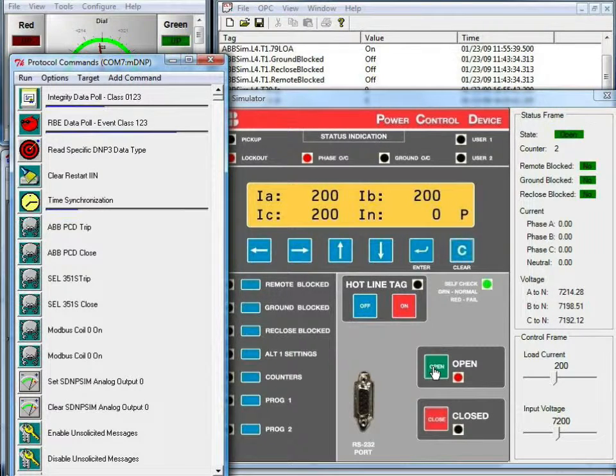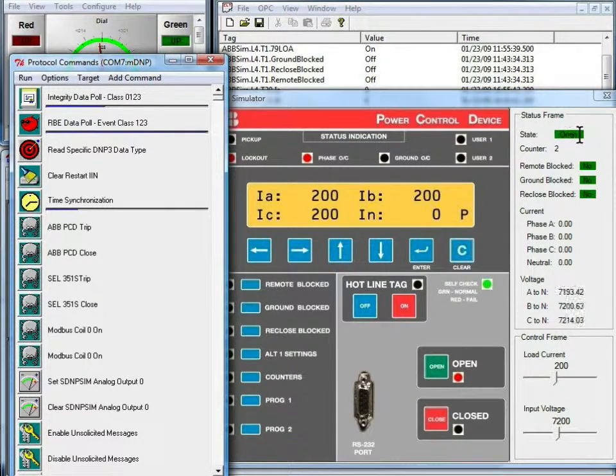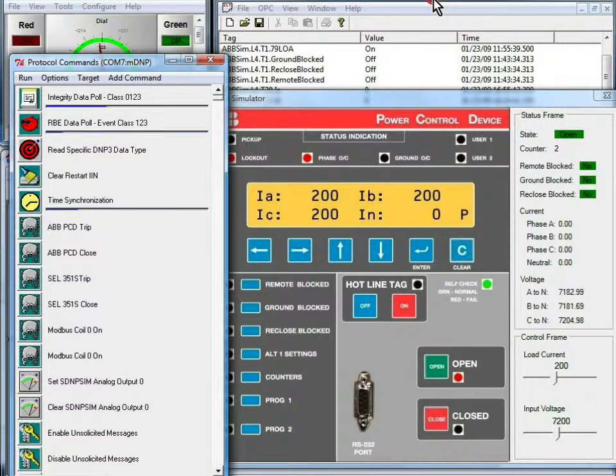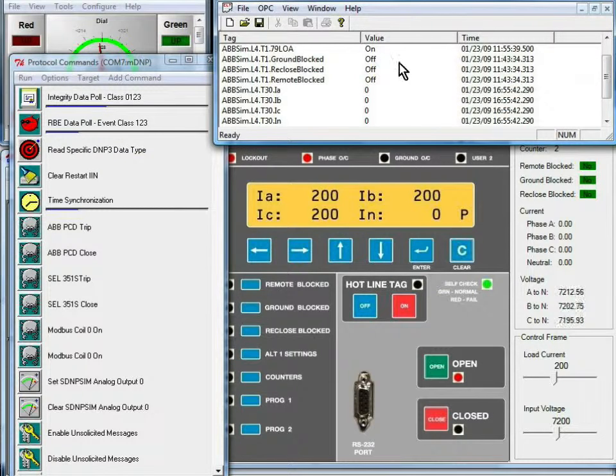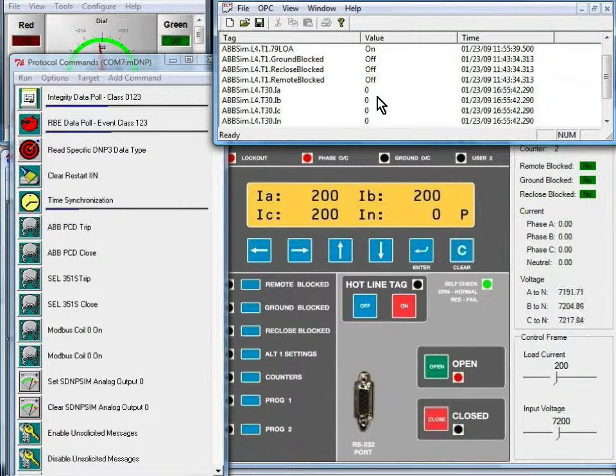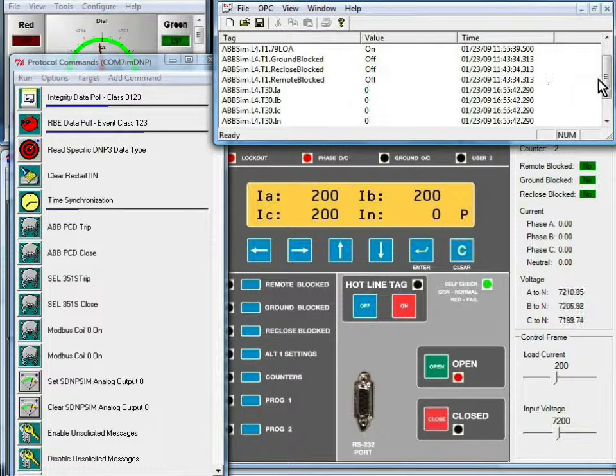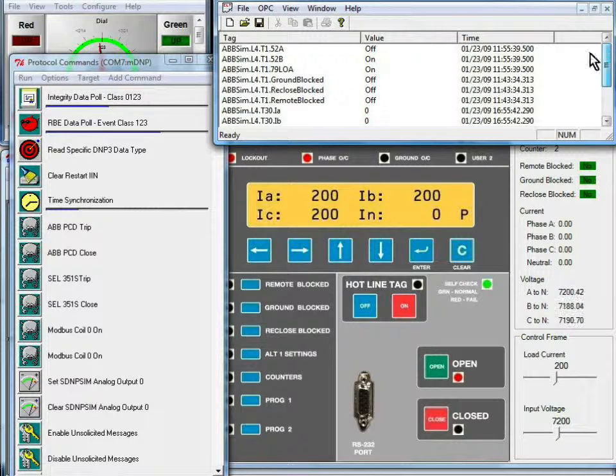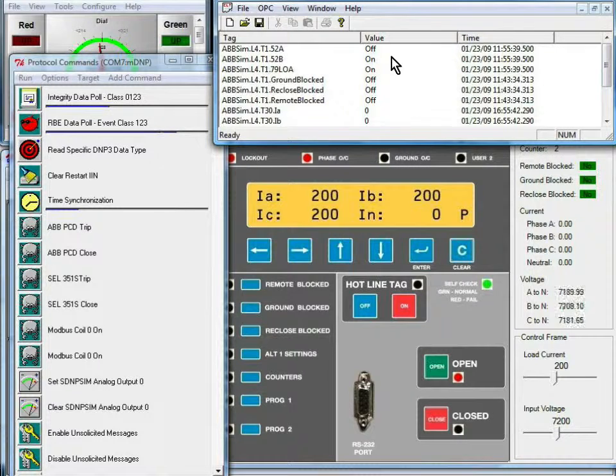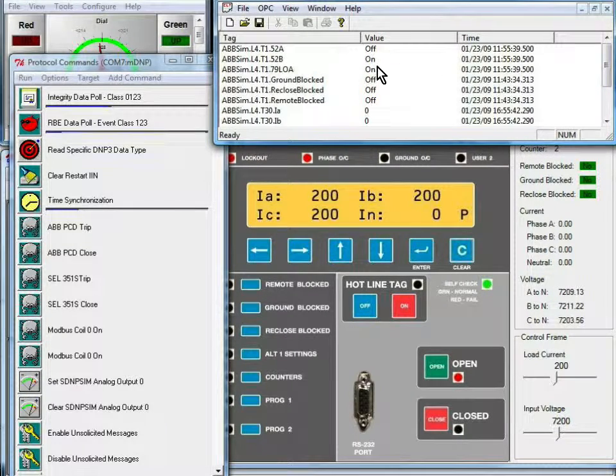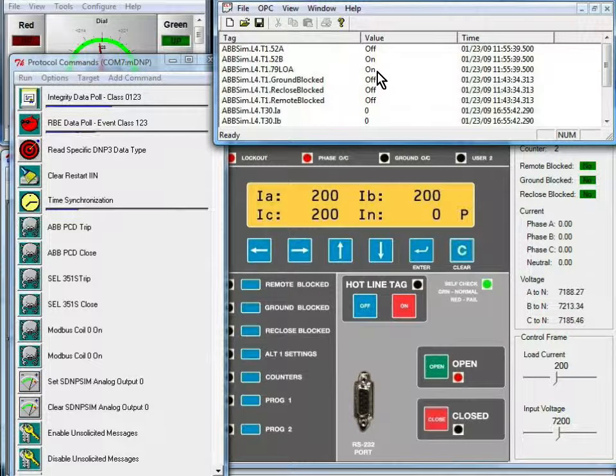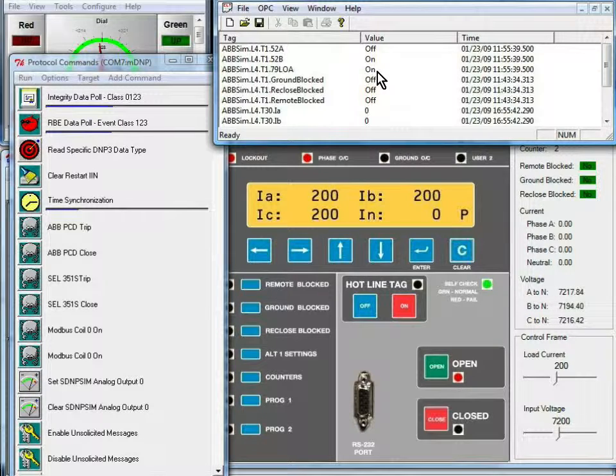Notice now the PCD is open. The state up here also shows is open. And if we go back and look in the OPC client, all of the currents are now zero. And if we look at the top status, they've changed as well. 52A is now off, and 52B and 79LOA are both on.